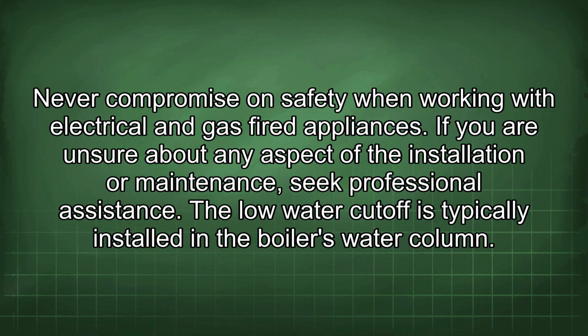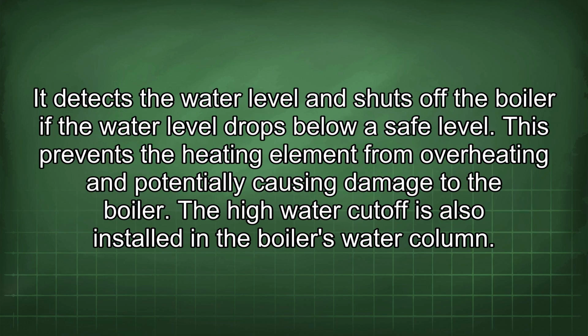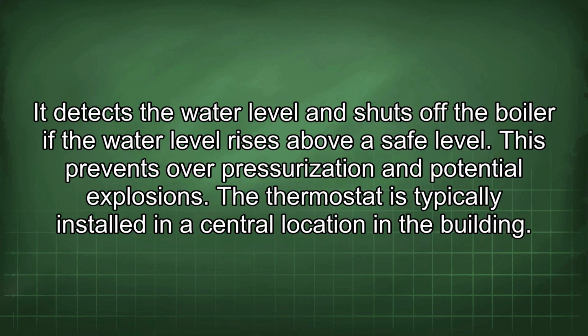The low water cutoff is typically installed in the boiler's water column. It detects the water level and shuts off the boiler if the water level drops below a safe level. This prevents the heating element from overheating and potentially causing damage to the boiler. The high water cutoff is also installed in the boiler's water column. It detects the water level and shuts off the boiler if the water level rises above a safe level. This prevents overpressurization and potential explosions.